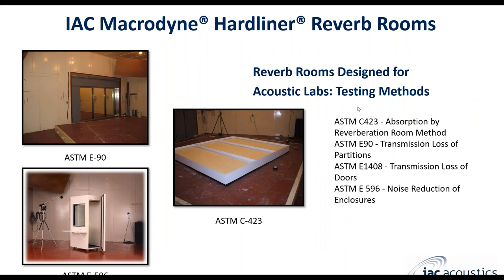Some of the typical tests required for these reverberation rooms come from providers and manufacturers for doors, windows, and absorbing materials in the automotive market. The ASTM series of sound level tests is pretty common, and most have ISO equivalents. ASTM C423 is a very common method for measuring absorption by reverberation room. You can see the photo here of the sample laid flat on the floor. Notice how the sample is not parallel to the surfaces of the room but is slightly crooked — there is a specific reason for that: to avoid standing room modes and any uneven distribution of sound.